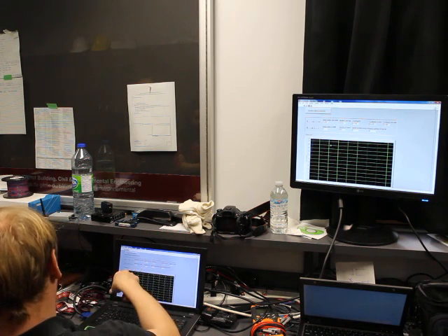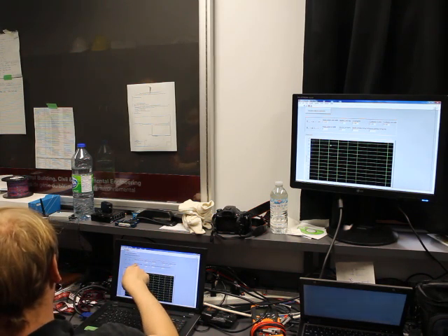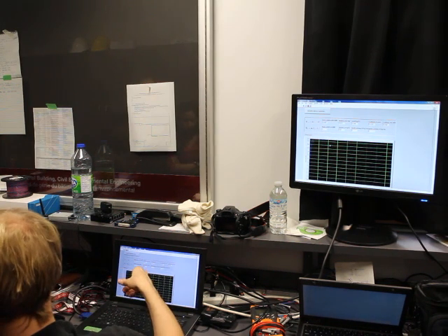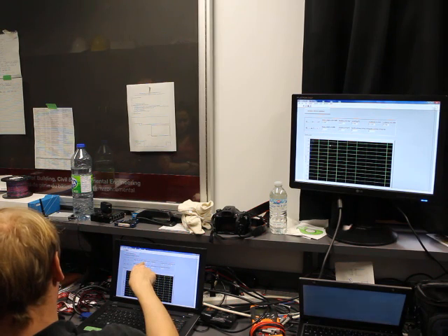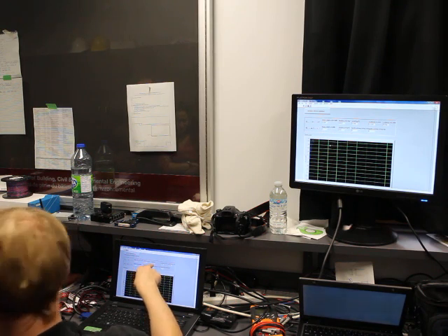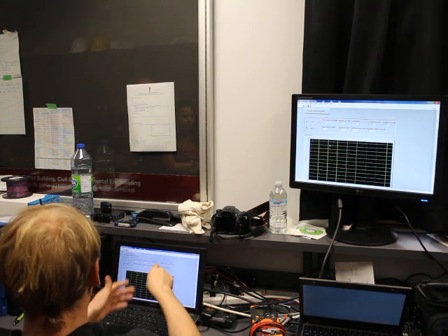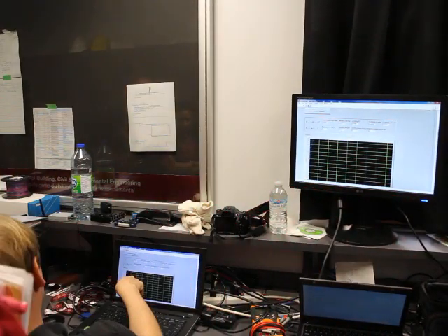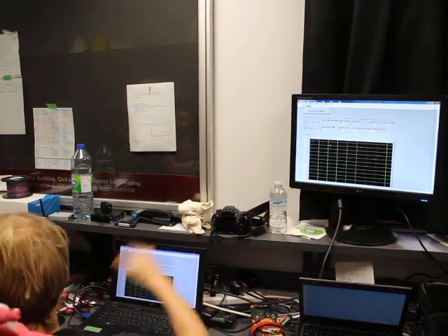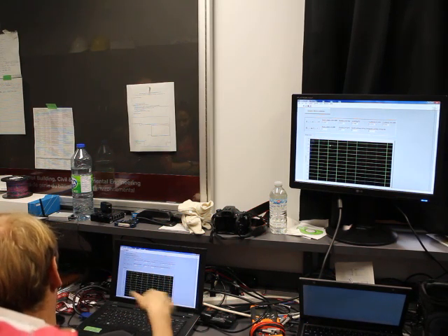So here you can always see the current power output of the collector. What is the power output? It is calculated by the mass flow, the specific heat capacity of the water, the temperature level, and the mean temperature in the collector. But you see, it's dropping at the moment because we increased the mass flow, so the power is getting lower.